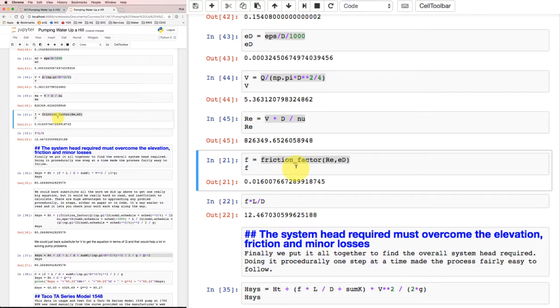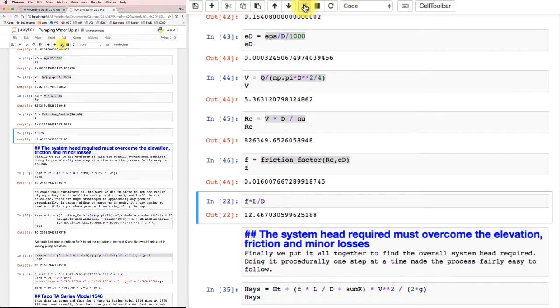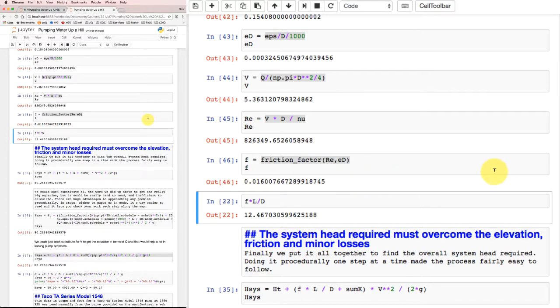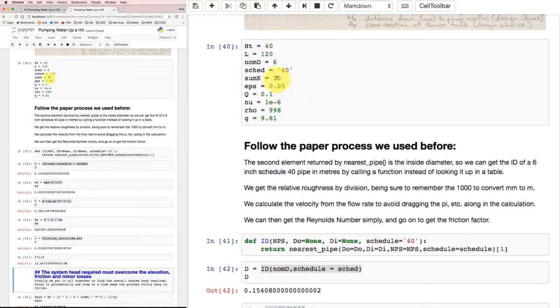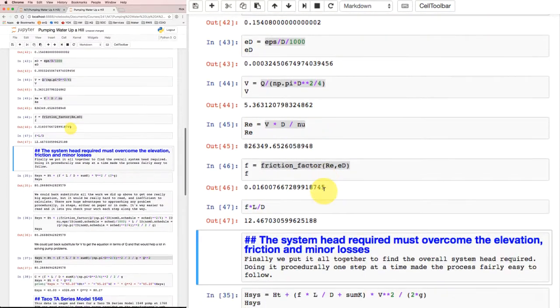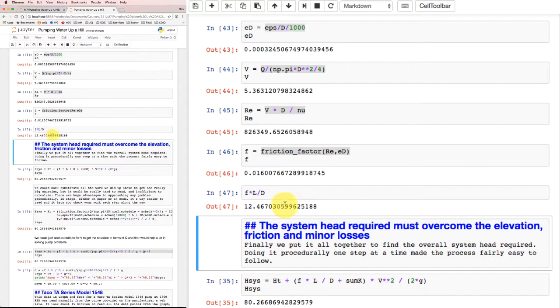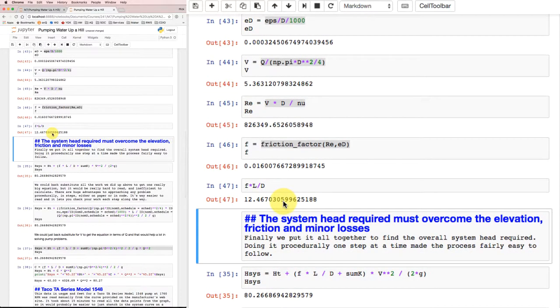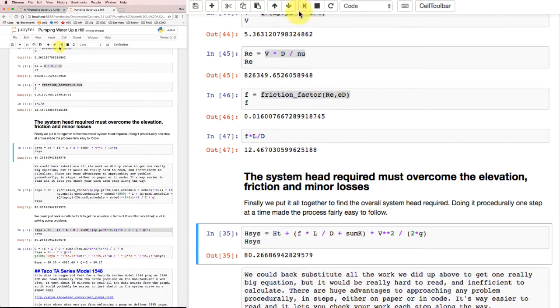I can calculate the friction factor. This function basically does a Moody diagram lookup if you supply it with the Reynolds number and the relative roughness. Last time I looked it up on the Moody diagram, but this time I'm going to run this function and get 0.016. So that agrees. Finally, I'll check what the product fL/D is. I get 12 and a half, which is what I got before on paper. That's 12.5 for friction compared to the sum of K values which was about 15. So about half our losses are going to friction in the pipe, and the other half to so-called minor losses. So the minor losses are actually a major component of the head loss.